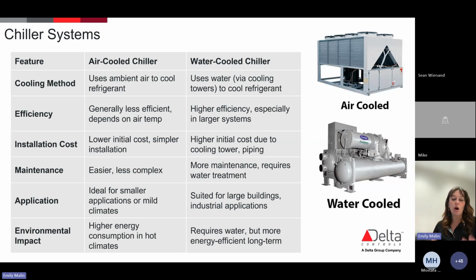But again, with water, you're obviously requiring water. So it just kind of depends on what you're going to be using and seeing inside of that building. But again, the important thing to notice here is, when you are starting to design that building automation system, this is yet another thing to bring up: what is going to be on site, whether or not you know that, hey, they already have air-cooled chillers or they have water-cooled chillers.